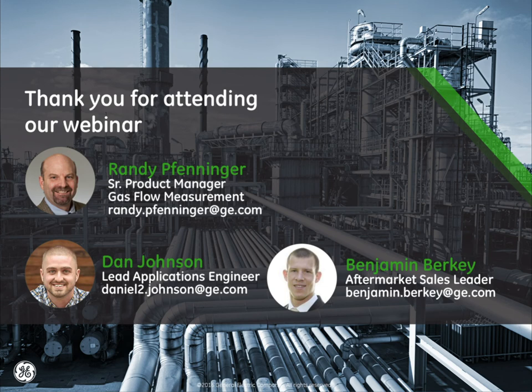Thanks, Randy, and I get this question a lot. You know, with the increasing regulations on flare flow meter service, the OEM recommendation is important, and GE's specific OEM recommendation is annual verifications. We feel that in order for the customer to get optimal performance out of the flare meter, we need to check the electronics and the structural integrity of that meter once a year. And by and large, that's become the industry standard from what I've seen.